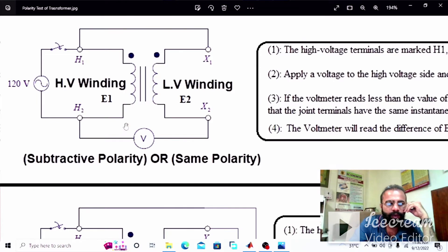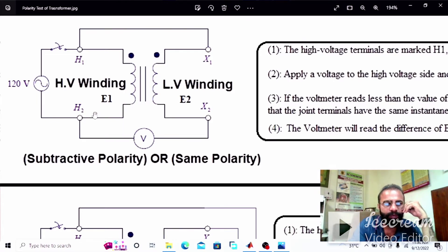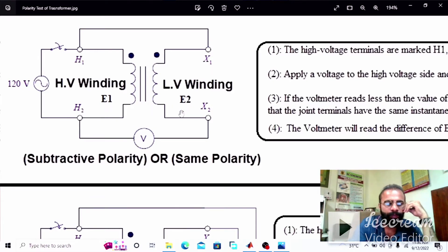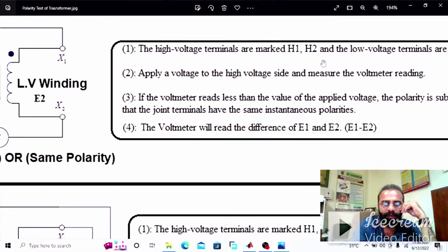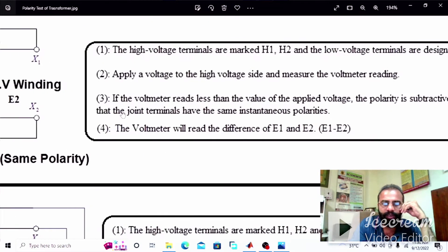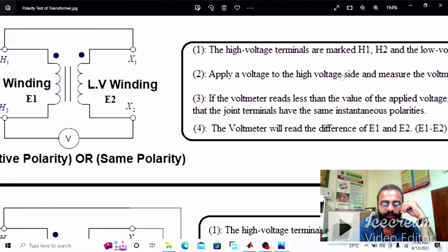Our first objective is to observe the results of the voltmeter when the transformer windings are connected in the same polarity. This is the diagram of the subtractive polarity. In this condition, the voltmeter will give us the difference of the two induced EMFs, E1 minus E2. H1 and H2 are the high voltage terminals and the low voltage terminals are designated as X1 and X2.